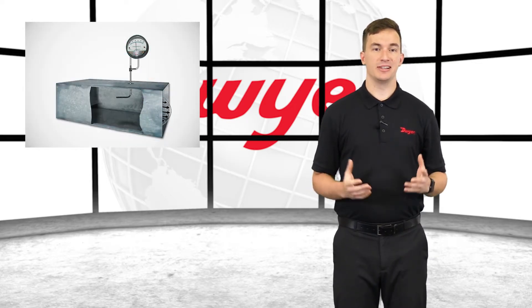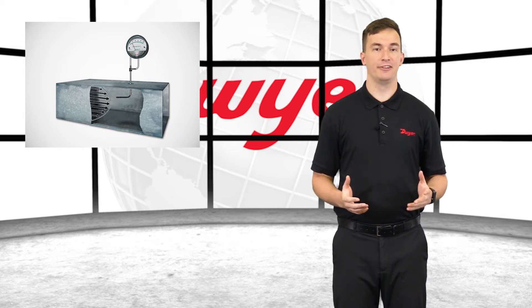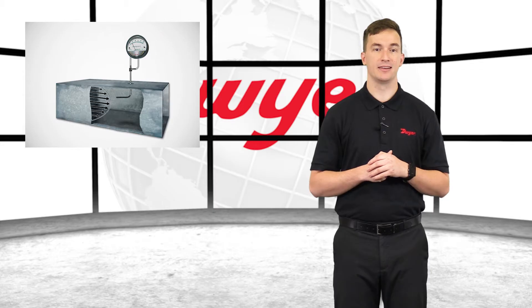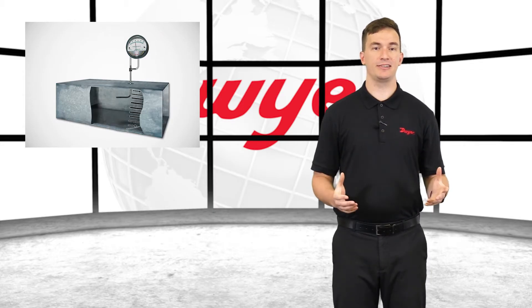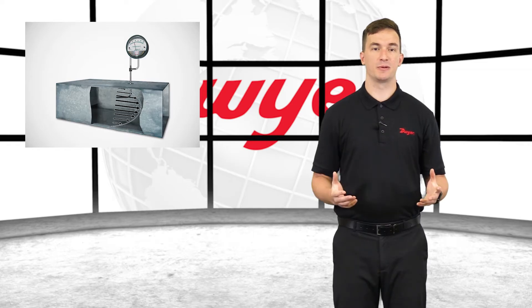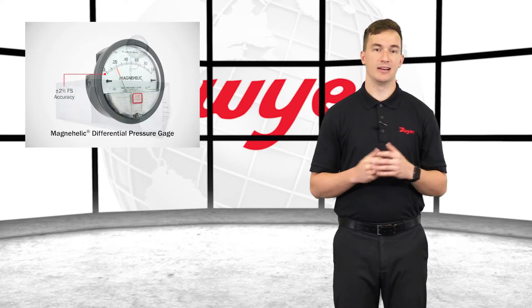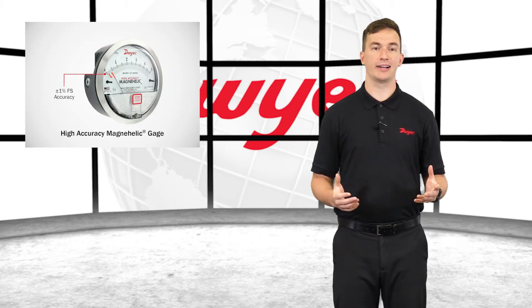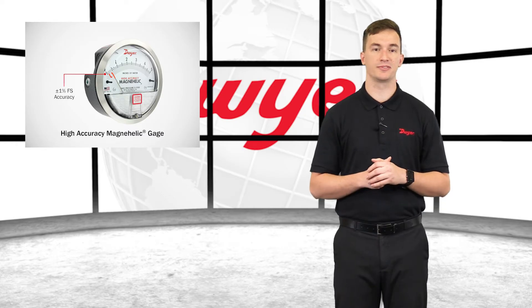This Differential Pressure Gauge is able to measure positive, negative, or differential pressures of air and other non-combustible gases. It uses an accurate and easy-to-read dial that is undistorted through the clear plastic face, which permits viewing from a distance. A standard Magnehelic gauge is accurate within 2% full scale, while the high-accuracy Magnehelic gauge is designed for accuracy up to 1% full scale.